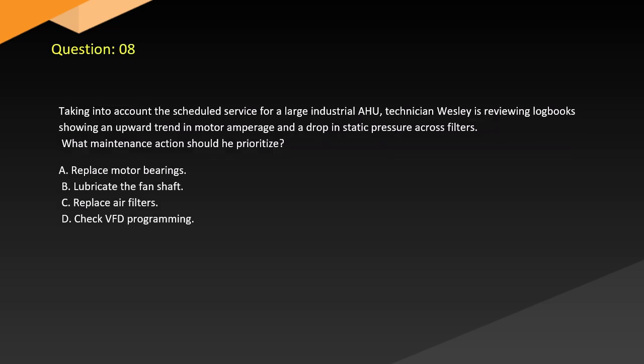Question 8. Taking into account the scheduled service for a large industrial AHU, technician Wesley is reviewing logbooks showing an upward trend in motor amperage and a drop in static pressure across filters. What maintenance action should he prioritize? A. Replace motor bearings. B. Lubricate the fan shaft. C. Replace air filters. D. Check VFD programming.